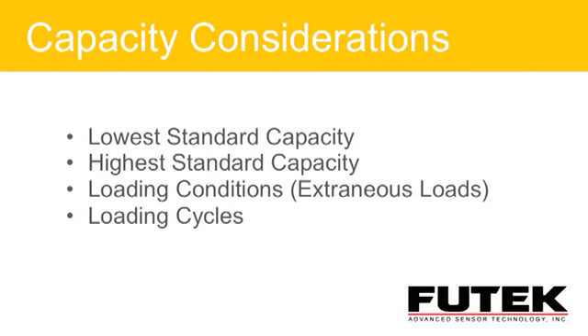You saw in a previous slide an S-beam with an S cutout. That does not like extraneous loads at all. But there are products that your sensor manufacturer, FUTEK, also has product categories that will survive extraneous loads much better. They're going to be accurate for that off-axis loading, for the side loads.